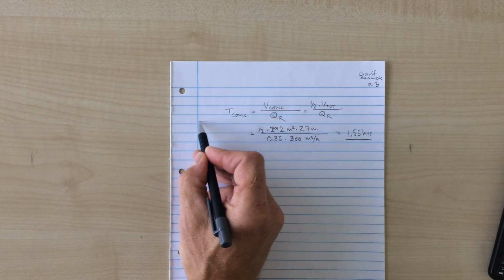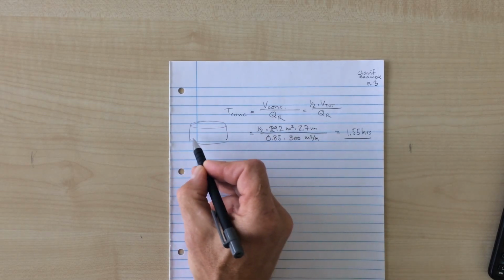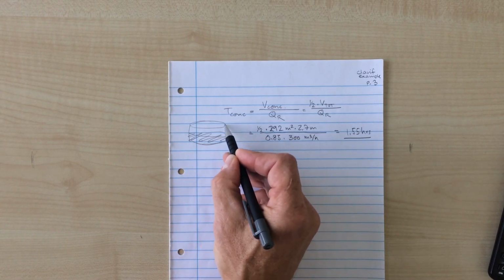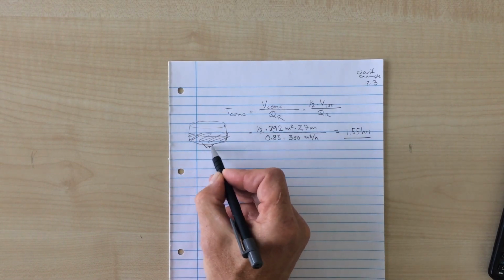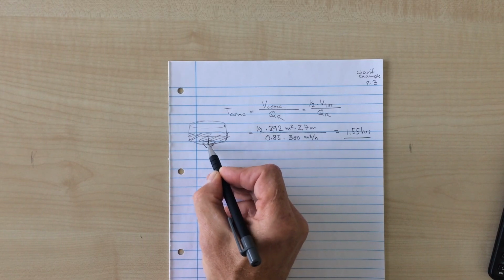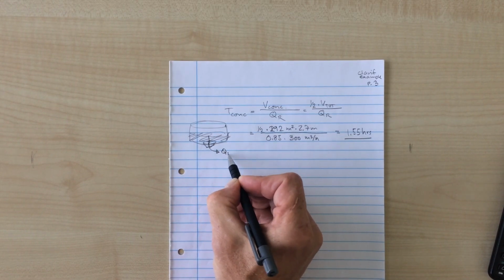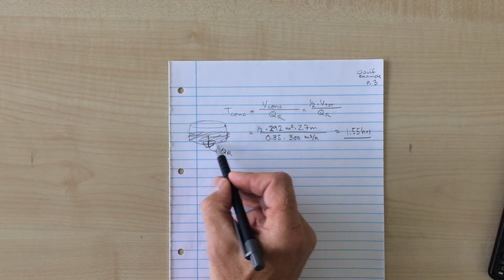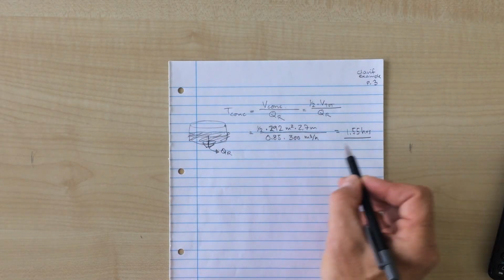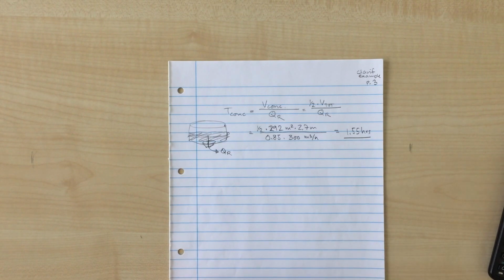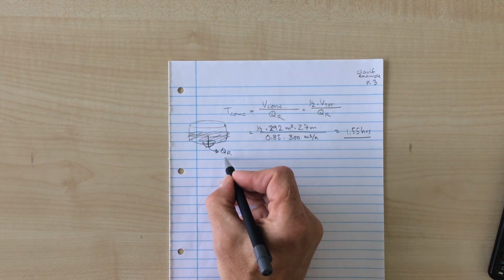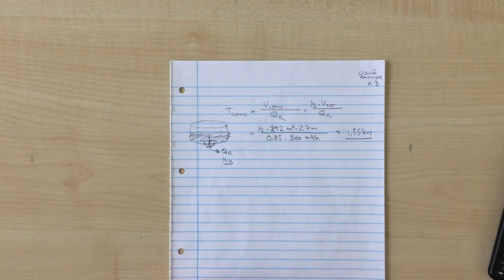So in the clarifier, if I allow the sludge to actually take up half of the total volume of the clarifier, this sludge will go down towards the outlet, the return sludge flow outlet, and that will allow the sludge to stay in here for 1.5 hours. The question is, what kind of concentration will I then arrive at? To answer that, I will have to look at my sludge concentration curve.